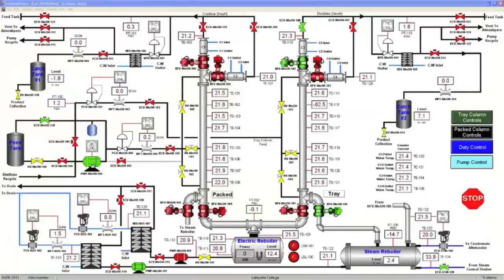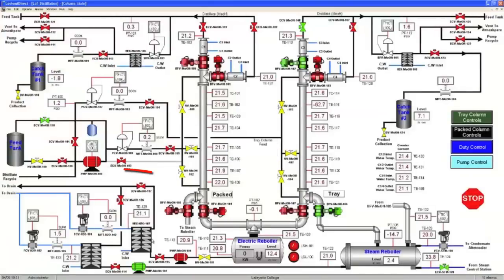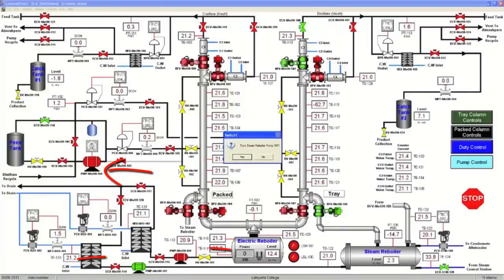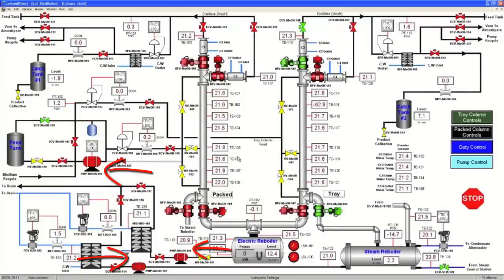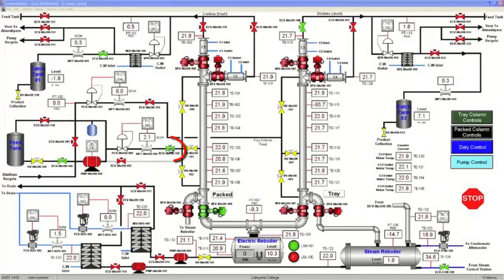Make sure all pumps are off: PMP MEOH 100, 101, and 102. On the HMI, close ECV MEOH 105 and 113 and open ECV MEOH 118.